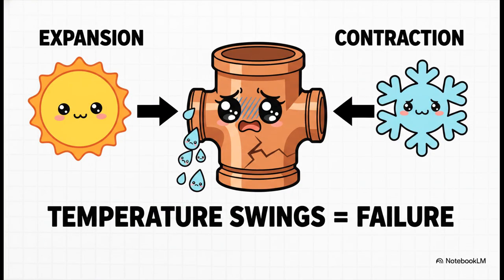This really shows the beating the climate puts on the cooling system. As temperatures swing like crazy, the copper tubing with refrigerant in it expands and contracts, over and over. After a while those joints get tired, they crack, and you end up with tiny leaks that bleed the life out of your air conditioner.